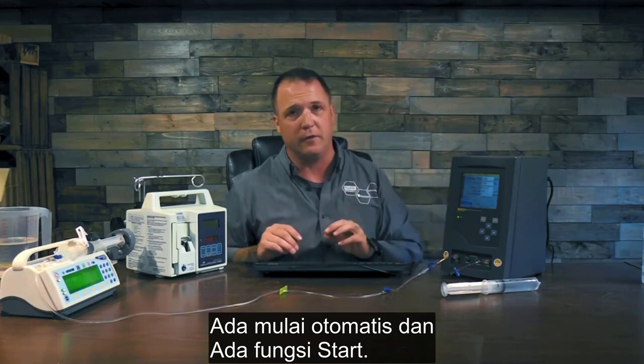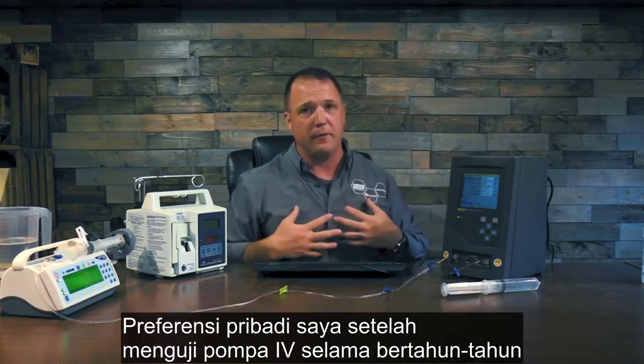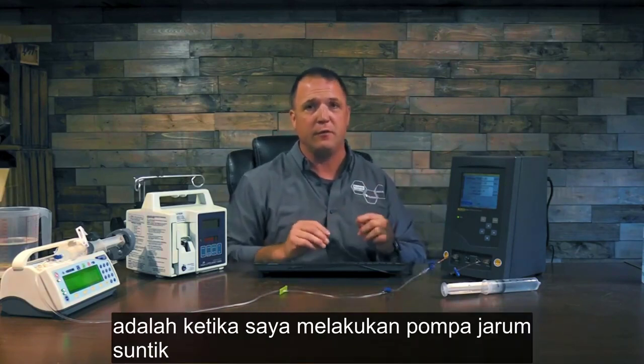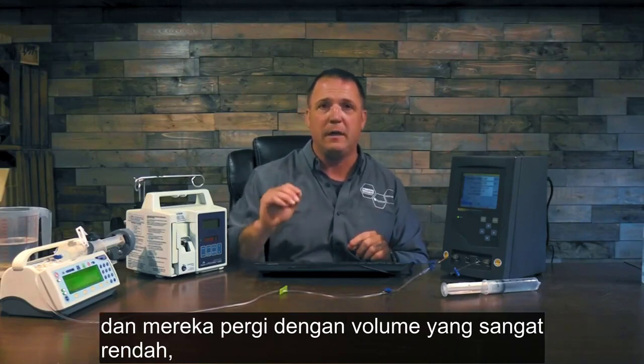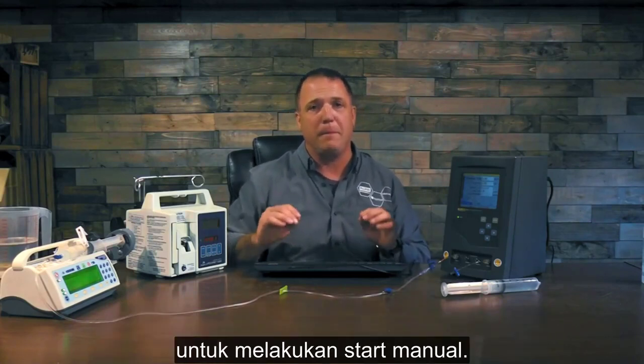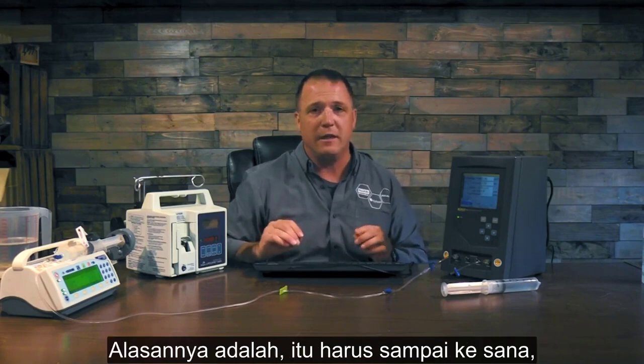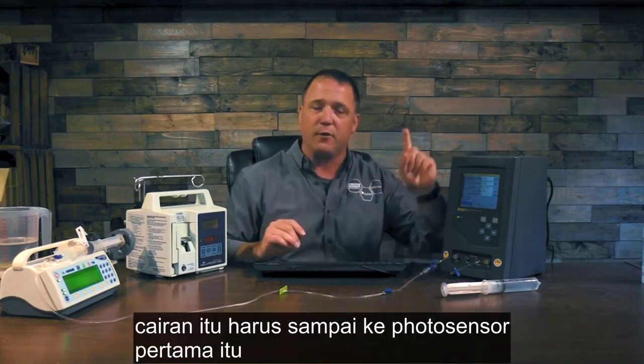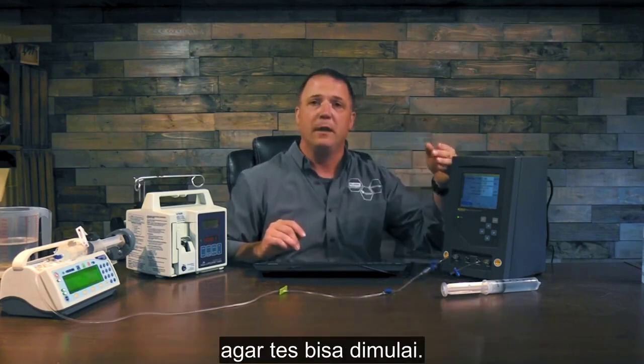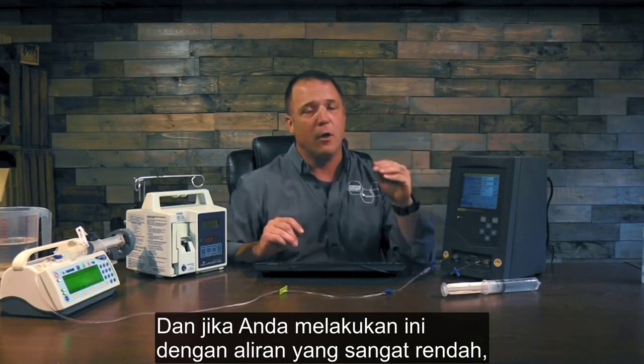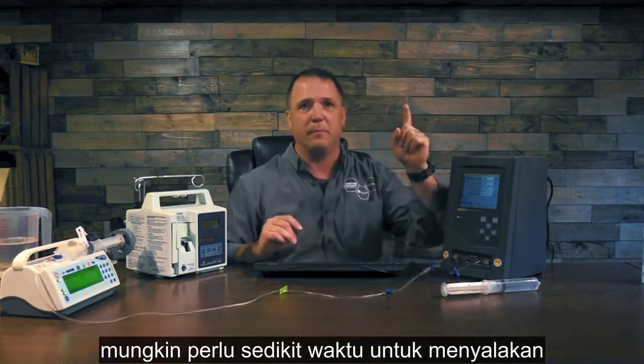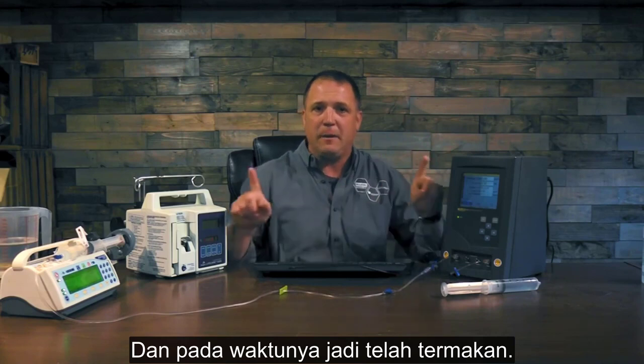There's two functions in here. There's an auto start and there's a start function. My personal preference after testing IV pumps for years, when I'm doing syringe pumps and they're going at a very low volume, is to do a manual start. The reason is the fluid has got to get to that first photo eye in order for it to trip. And if you're doing this with a very low flow, it might take a little bit for it to trip that first photo eye. And that time has gone on.